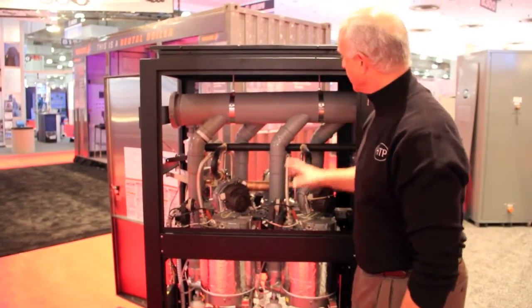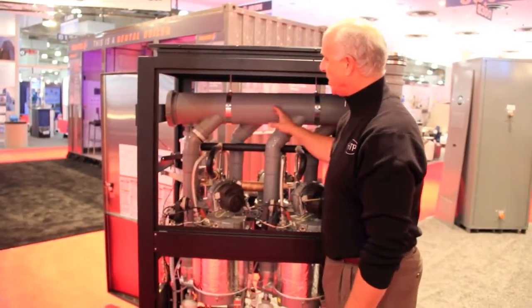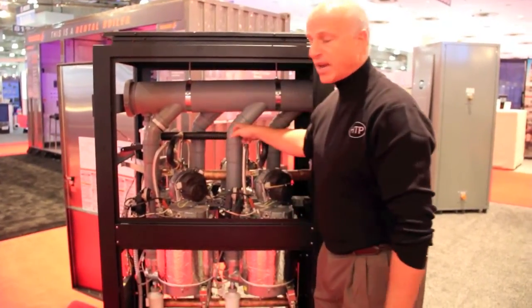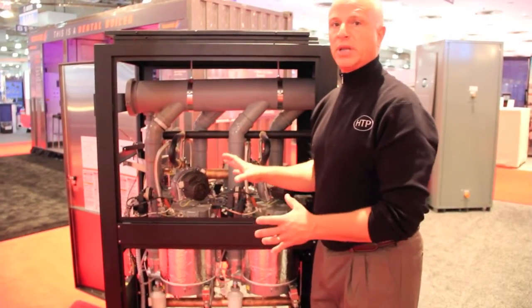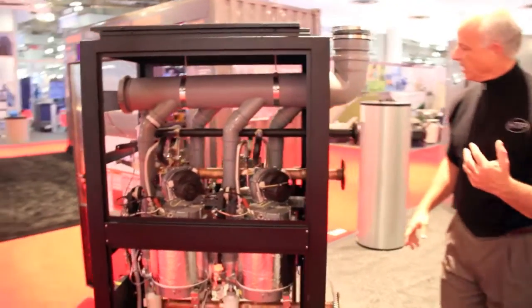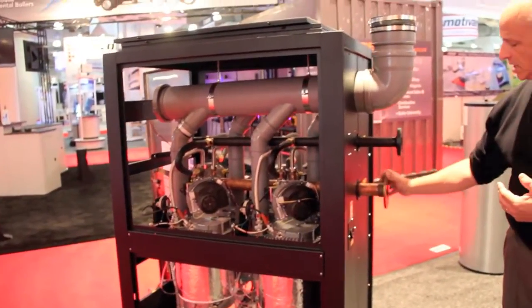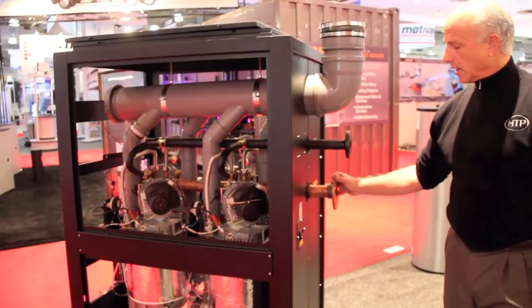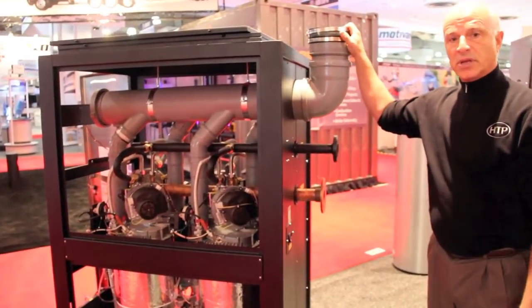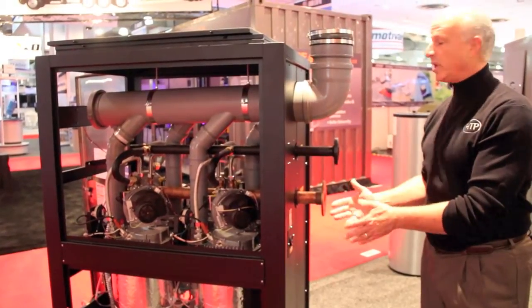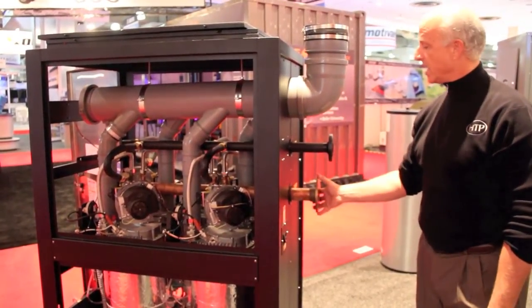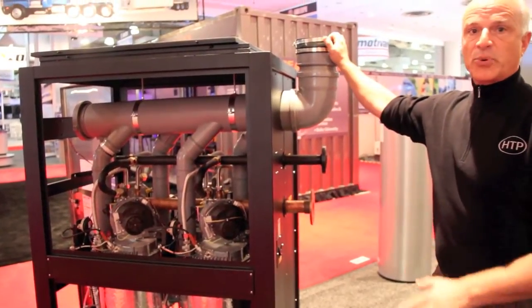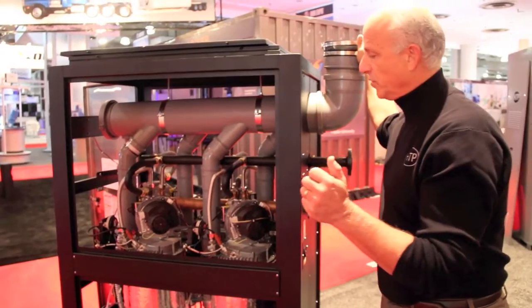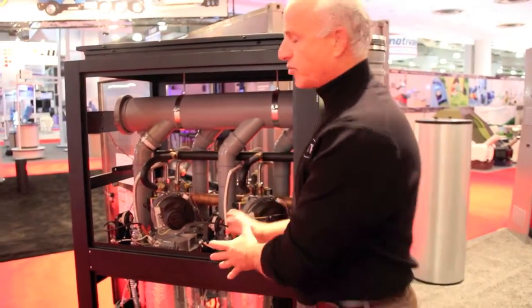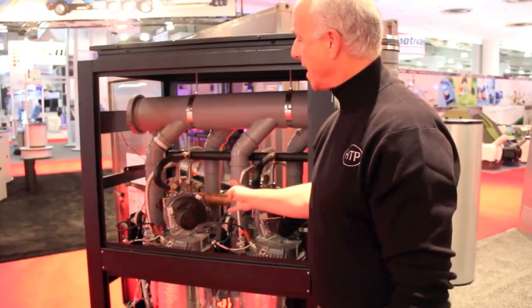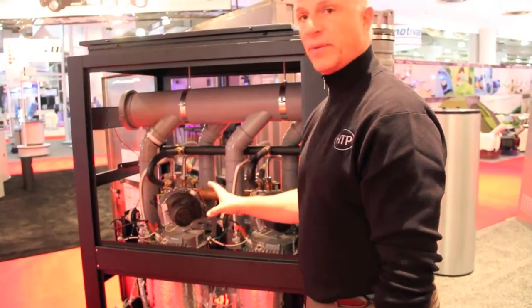Kind of looking into this device, you can see, as I was saying earlier, you got your manifold all pre-done. You got your flexible gas piping that's all manifolded for your customers. So this comes as one complete unit. As you pan over here, you can kind of see that we have connections. We got our gas connections, our incoming water, our outgoing water. We've got our vent connections. So all the manifolds, the customers just take this unit. They have 2 connections for their domestic in and out, their gas piping. On their vents, it's all pre-done for them, so there's no manifolding like you would have to do with the 250. It's all completely done. It comes in one attractive box. It's all wired, electrically wired, and it's already pre-wired and plumbed for the customers.